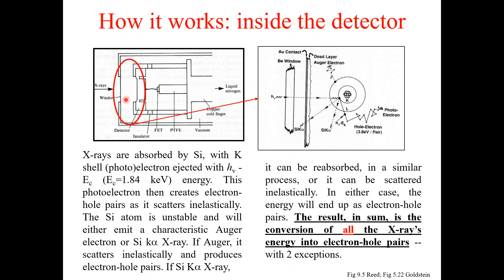Inside the detector, when x-rays interact with the detector, the x-rays are absorbed by the silicon crystals. This portion has been enlarged and shown separately. An x-ray of particular energy comes through the window and interacts with the silicon crystals — specifically with the inner shells — and an electron is ejected with a corresponding amount of energy. This ejected electron is called the photoelectron, and the photoelectron then creates electron-hole pairs as it scatters inelastically in the material.